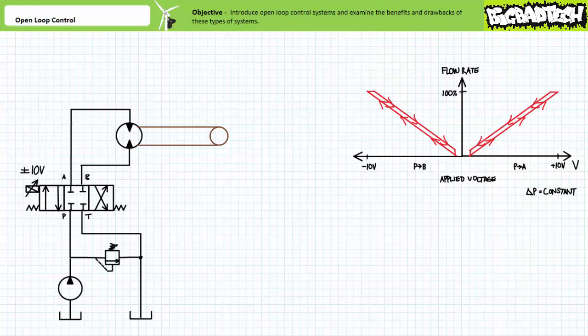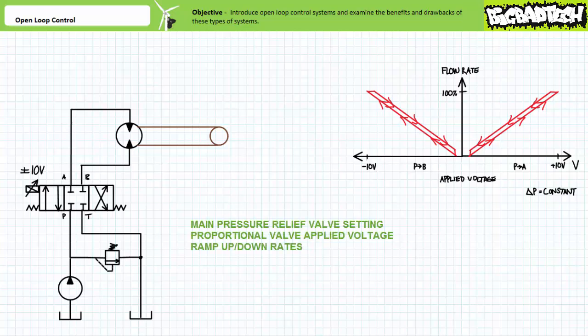At installation and commissioning, a technician is responsible for establishing several base settings: one, the main pressure relief valve setting; two, the voltage magnitude that positions the spool such that the steady state flow rate results in the conveyor moving at an appropriate speed; and three, the ramp-up and ramp-down rates such that the conveyor belt doesn't jerk to a start and slam to a halt. For open-loop control purposes, the technician is making use of a non-contact laser tachometer to read the resultant speed of the hydraulic motor. These respective values are initially set at 700 psi, positive 10 volts, and four seconds for both ramp-up and ramp-down time.